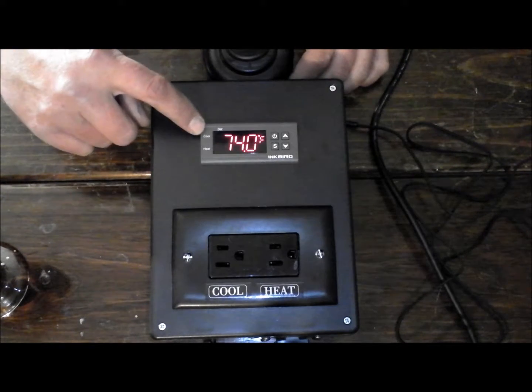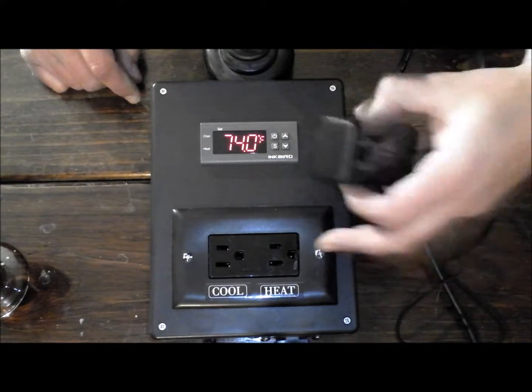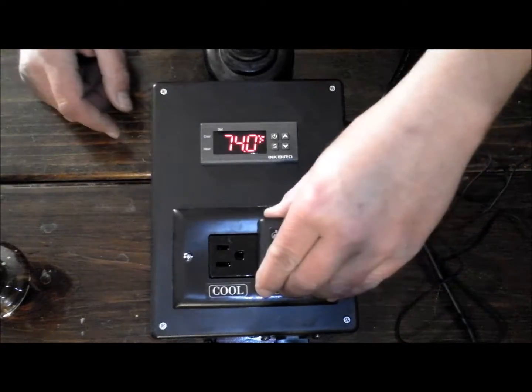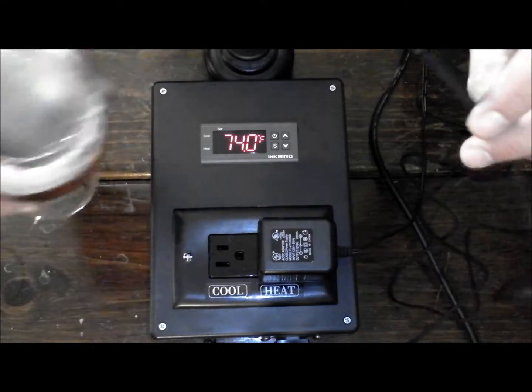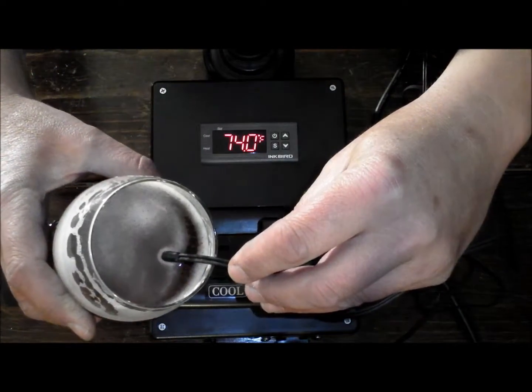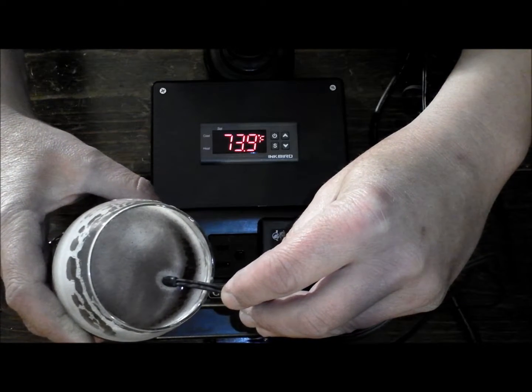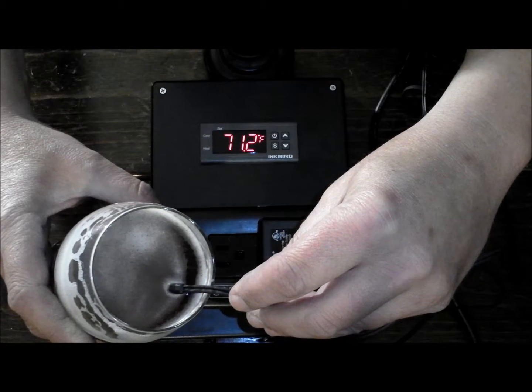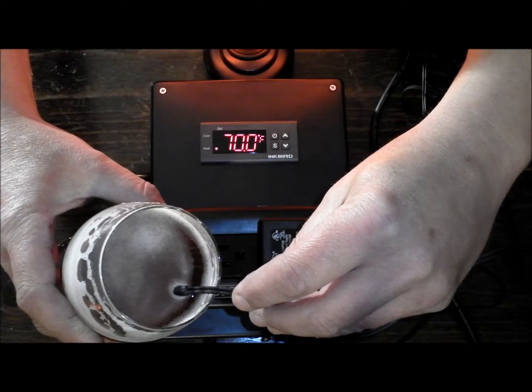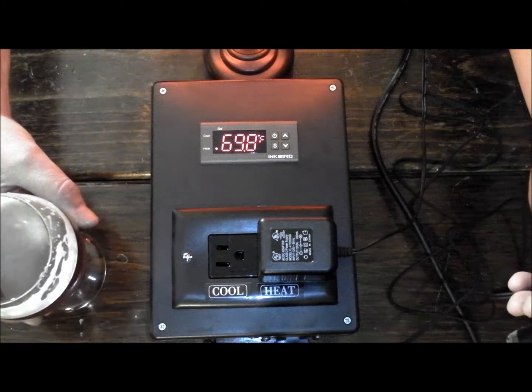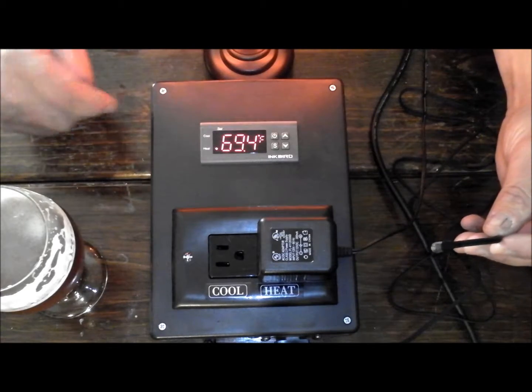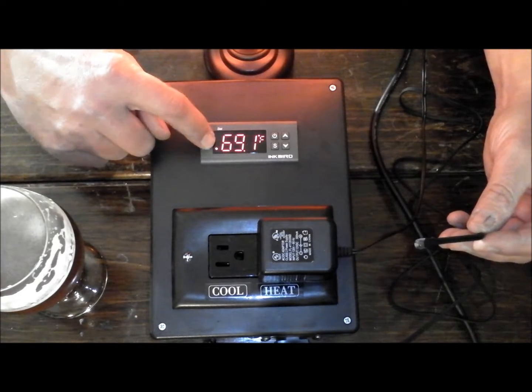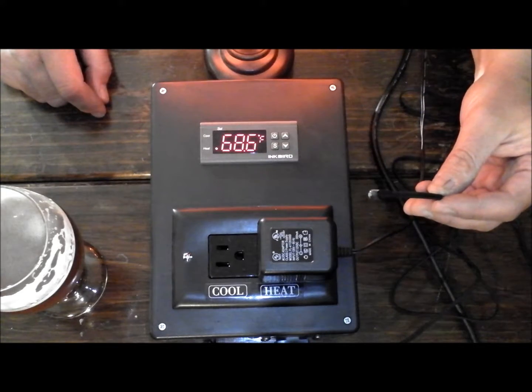You can see there's a cool and a heat indicator over here. What I'm going to do is, into the heat, we'll plug in our little light here. And I'm going to take this temperature sensor, and we'll dip it into the end of a beer. Now this sensor isn't super reactive, but the temperature swings aren't going to be real drastic. And you can see right there, as soon as it got down below 70 to 70 degrees, it called for the heat to come on. See the little indicator there? The fact that our light lit up tells us that we have power going to the heat.